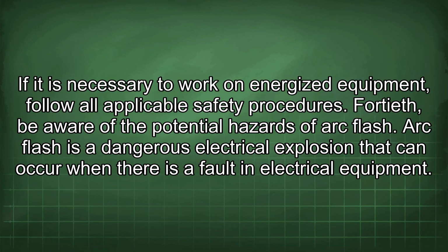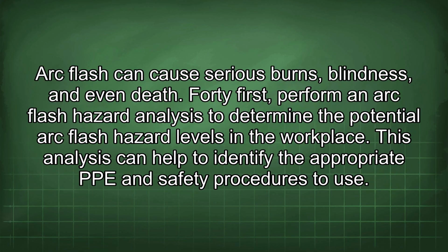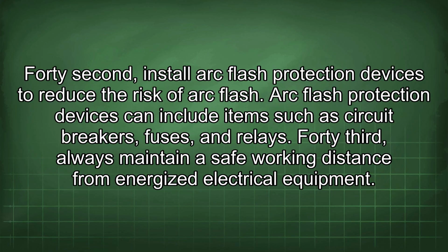40th, be aware of the potential hazards of arc flash. Arc flash is a dangerous electrical explosion that can occur when there is a fault in electrical equipment. Arc flash can cause serious burns, blindness, and even death. 41st, perform an arc flash hazard analysis to determine the potential arc flash hazard levels in the workplace. This analysis can help to identify the appropriate PPE and safety procedures to use. 42nd, install arc flash protection devices to reduce the risk of arc flash. Arc flash protection devices can include items such as circuit breakers, fuses, and relays.